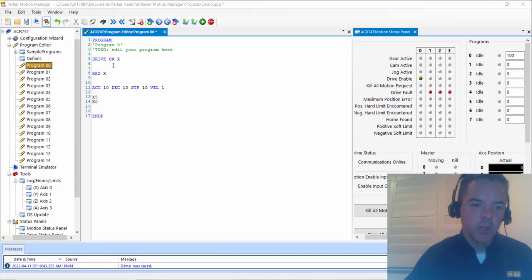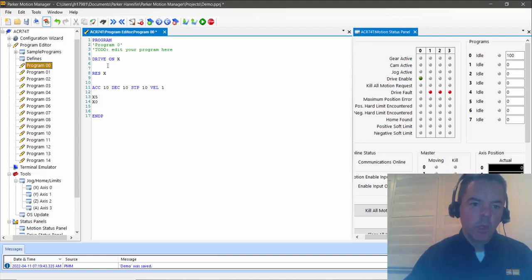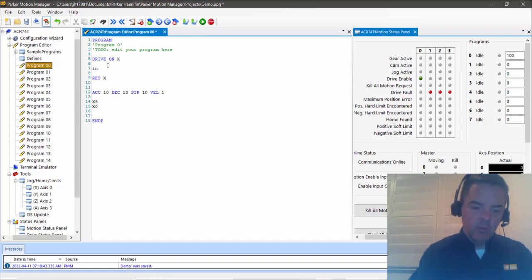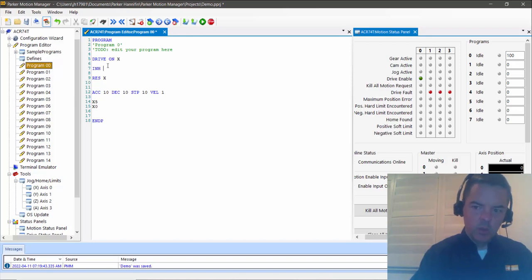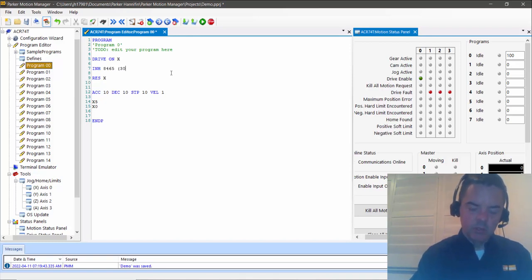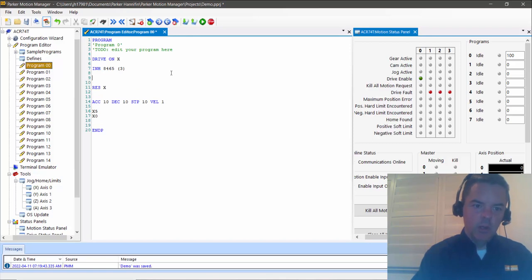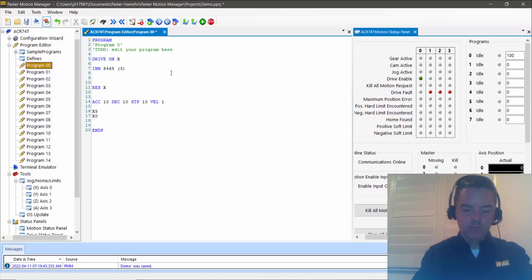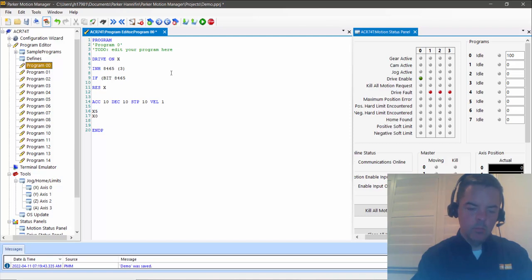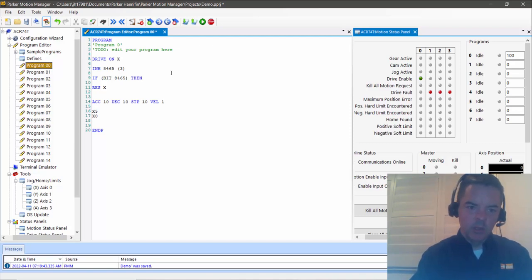So we've enabled the motor and got basic motion. After we enable the drive, we'll actually check to make sure that the drive enables. We would want to inhibit on bit 8465 and let's give it up to three seconds. Then let's check if, and we can do this with an if-then statement.